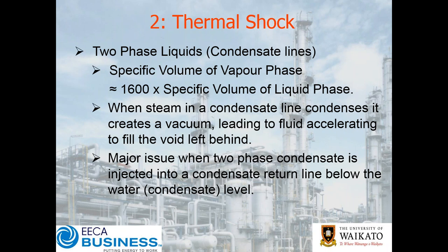What we can introduce if we're not careful is a whole lot of mini explosions. If those mini explosions are occurring across a valve seat, ultimately over time the force of that explosion is enough to actually erode the valve seat. The same thing with the orifice of a steam trap or any other piece of equipment. If you start thinking about them in those terms — instead of 'water hammer,' how about we rename them 'uncontrolled explosions' and see what our safety person has to say about that?